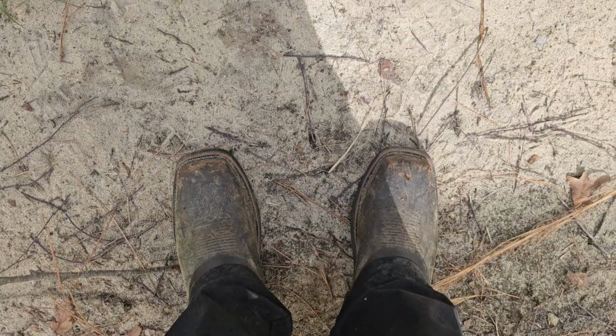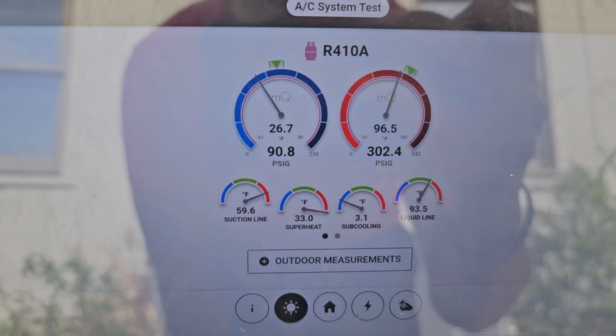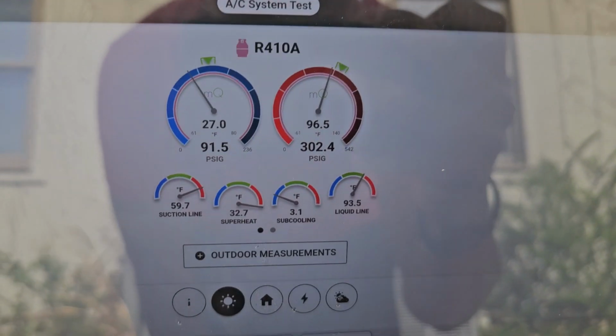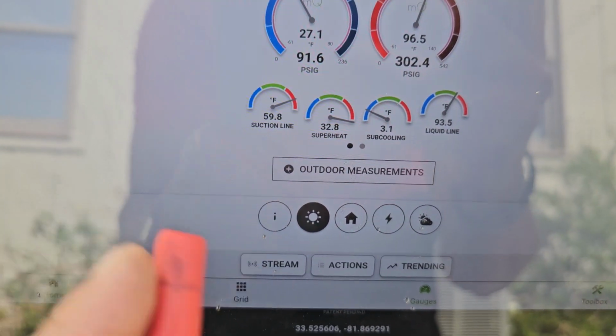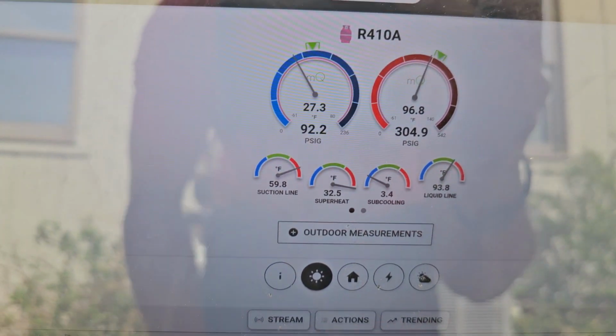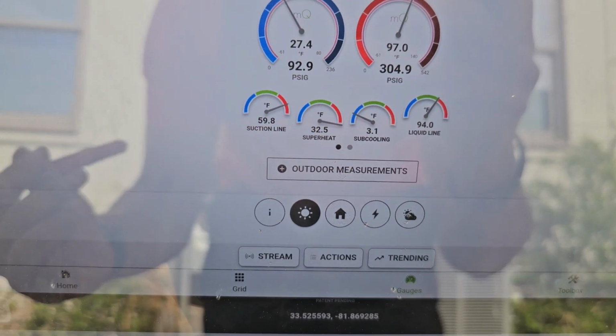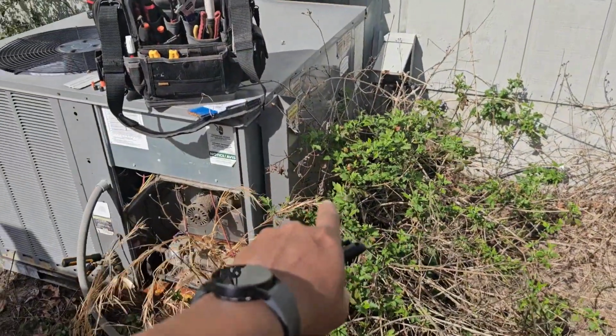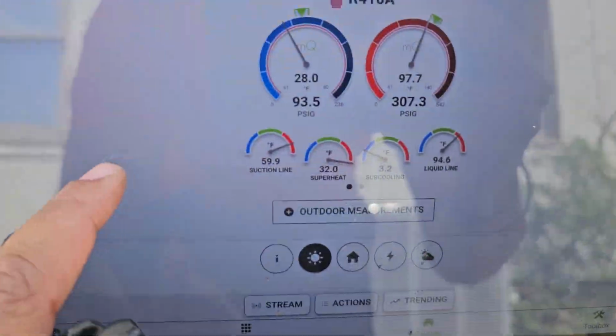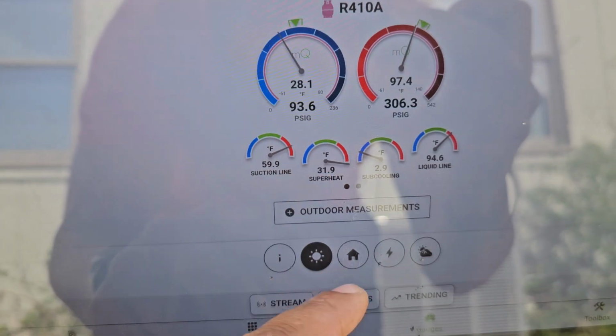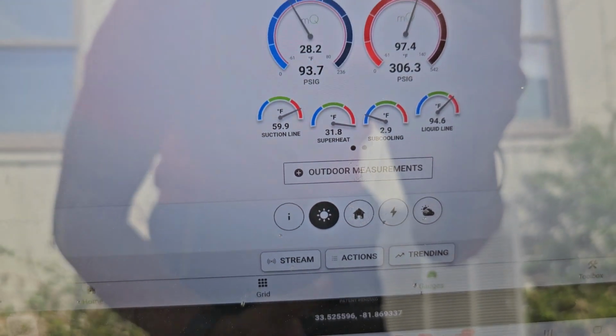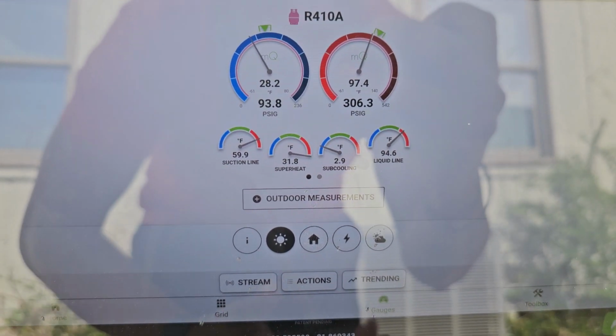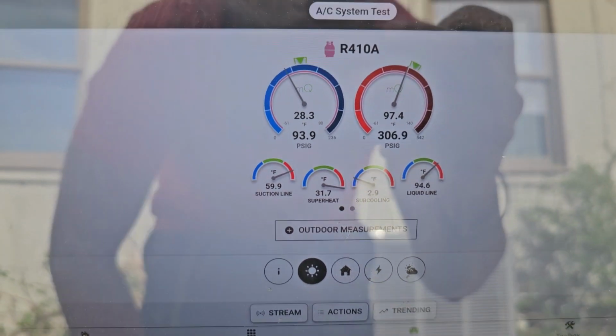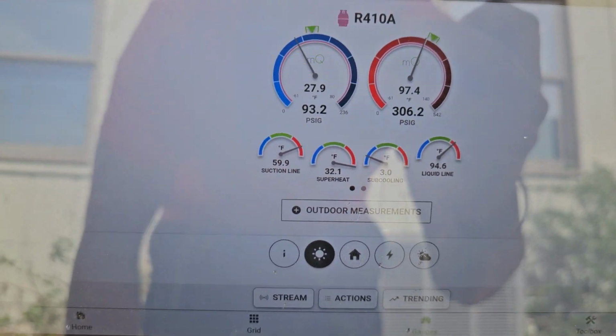My screen don't want to stay on for nothing. And I'm wondering if Measure Quick is going to tell us we're low also. But even if I wanted to base it off superheat or subcool, I don't know if it's a TXV or a piston, because I'm not about to cut my hand up messing with all that stuff right now. But you could understand that high superheat would normally, on a piston system, indicate a low charge, depending on your piston size and the manufacturer data specs.